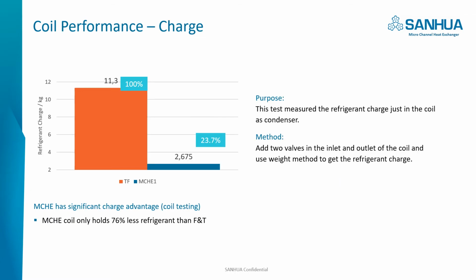The next item is about charge. Charge is quite critical to the new A2L refrigerant system design, so we need to find the difference between microchannel and fin and tube heat exchangers. Because we don't have the unit in our in-house laboratory, we found a new way to test the charge for the coil only. Because the condenser holds more refrigerant than the evaporator, we measure the refrigerant charge after the condenser performance testing. We added two valves in the inlet and outlet pipeline of the coil, and we used the weight method to get the refrigerant charge.